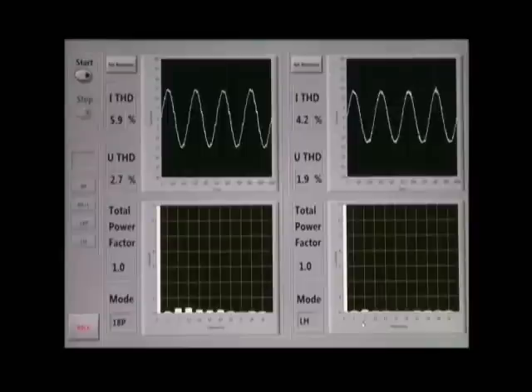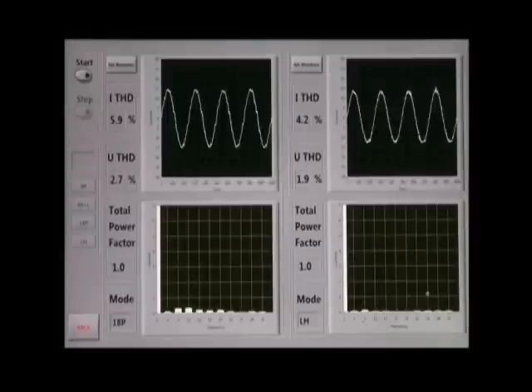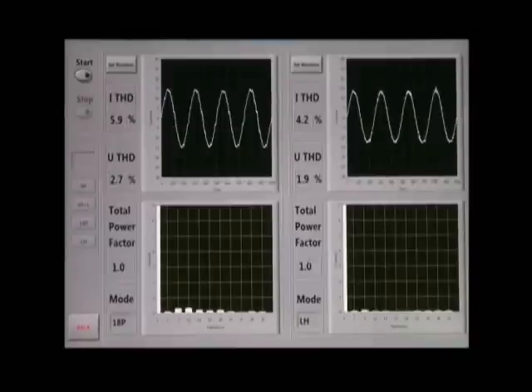Looking at the graphs to the bottom of the screen, we do see individual harmonic levels, even in the 18-pulse, in the 7th, 11th, 13th harmonics. Moving over to the ULH, these levels are almost imperceptible, even on the graph. Once again, our comparison of all types of technologies has proven that the ULH technology provides the best level of harmonic mitigation, both in current and voltage distortion, while providing a power factor of unity and additional benefits that we'll discuss in a moment.